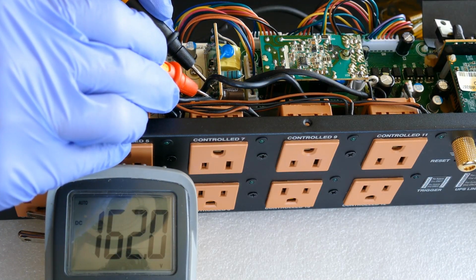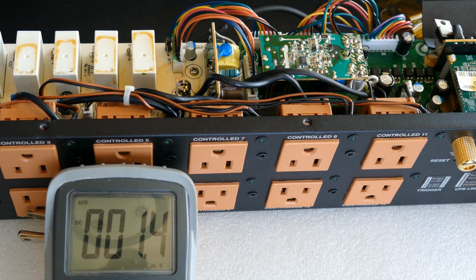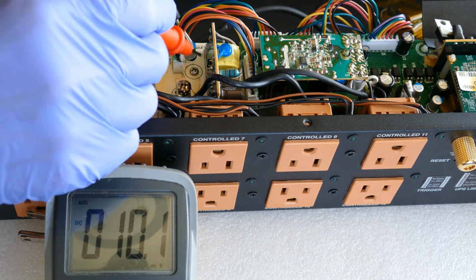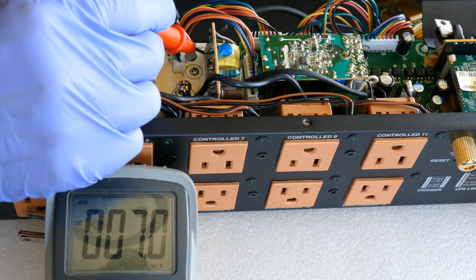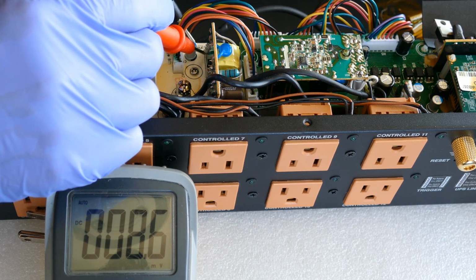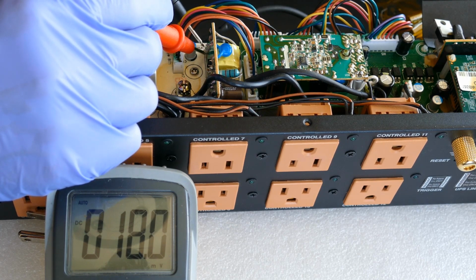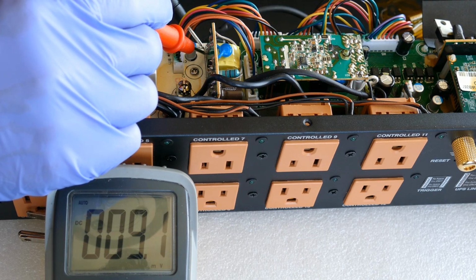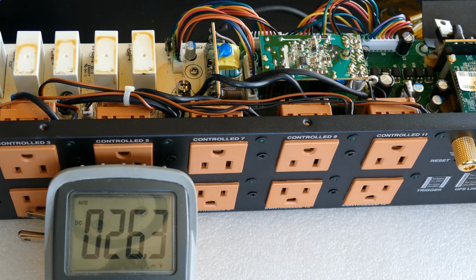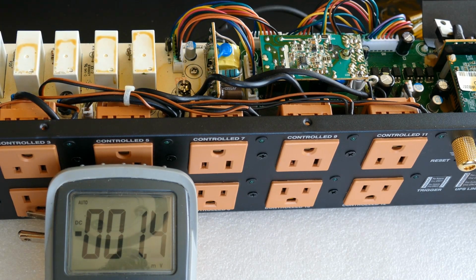There's 162 volts DC on the output side of the power board's bridge rectifier, so it's getting power, and the rectifier is working. However, there's no power on the low voltage output side of the board. This suggests a failed power board, or possibly a short on the relay board that it powers, although I already tested the relay board when it was out and I didn't find any problems.